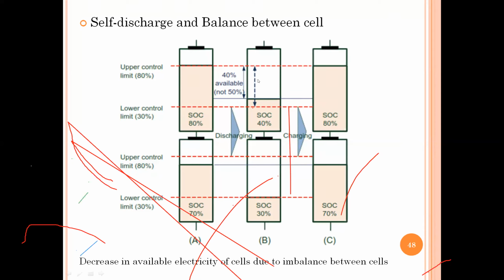It can't able to utilize it. Actually 50% SOC should this battery utilize, but only it is utilizing 40%. The full capacity is not able to utilize. When you go for the discharging, this will reach to the lower control limit of the SOC, that is 30%, and this is not going to reach to its lowest capacity. It is utilizing only 40% of available power, SOC.